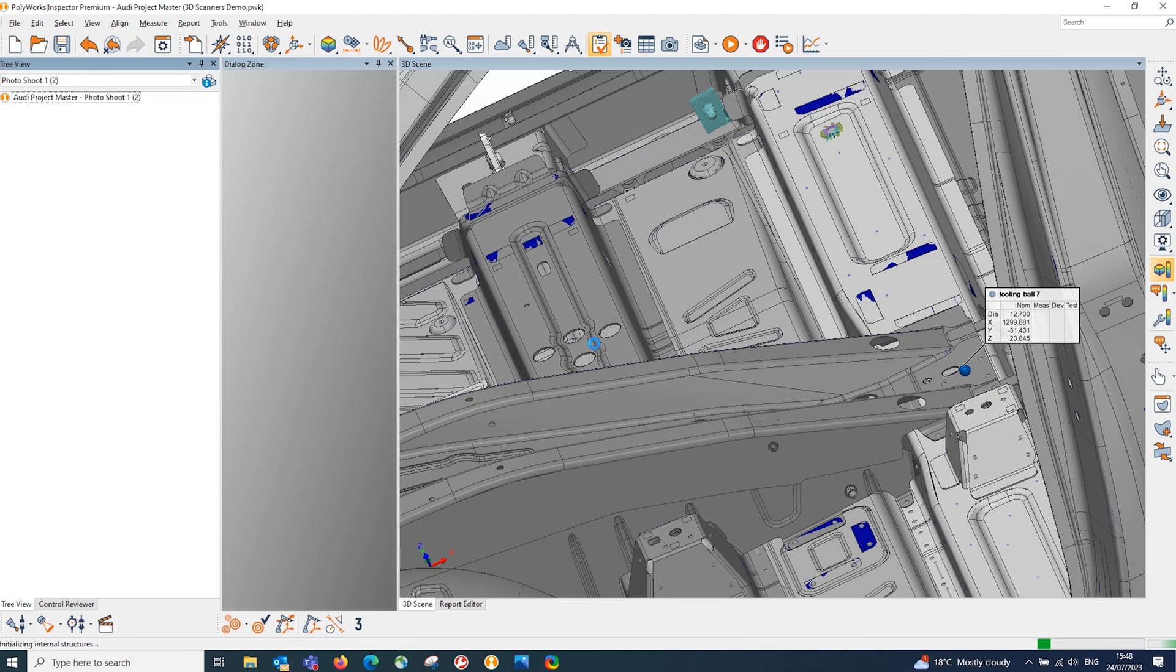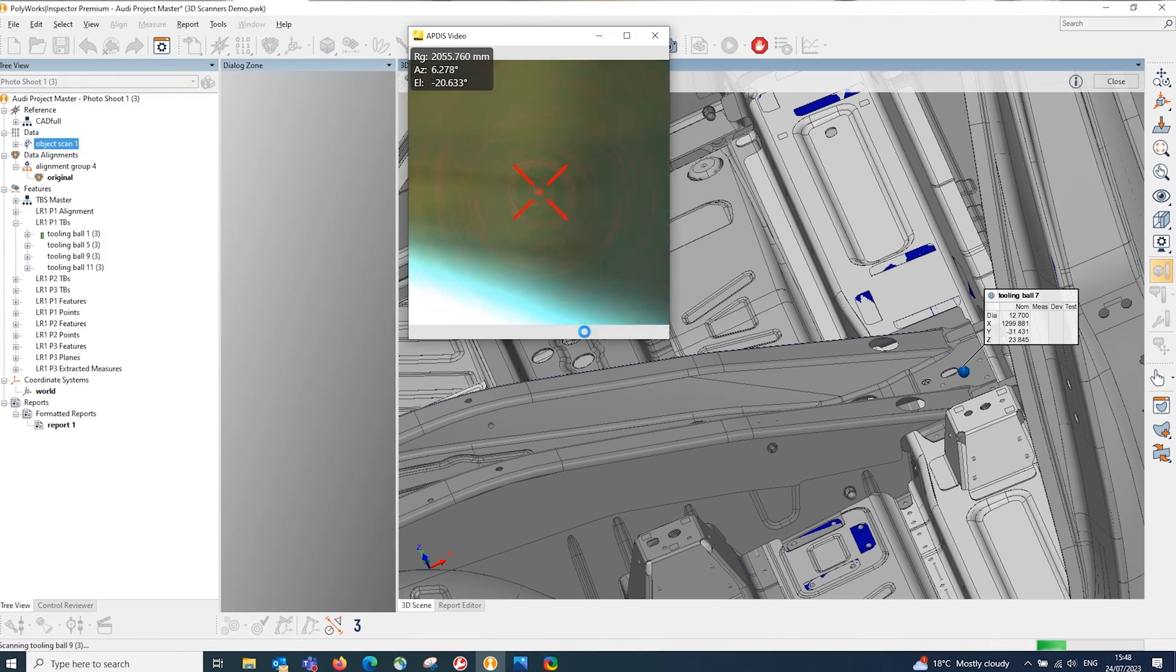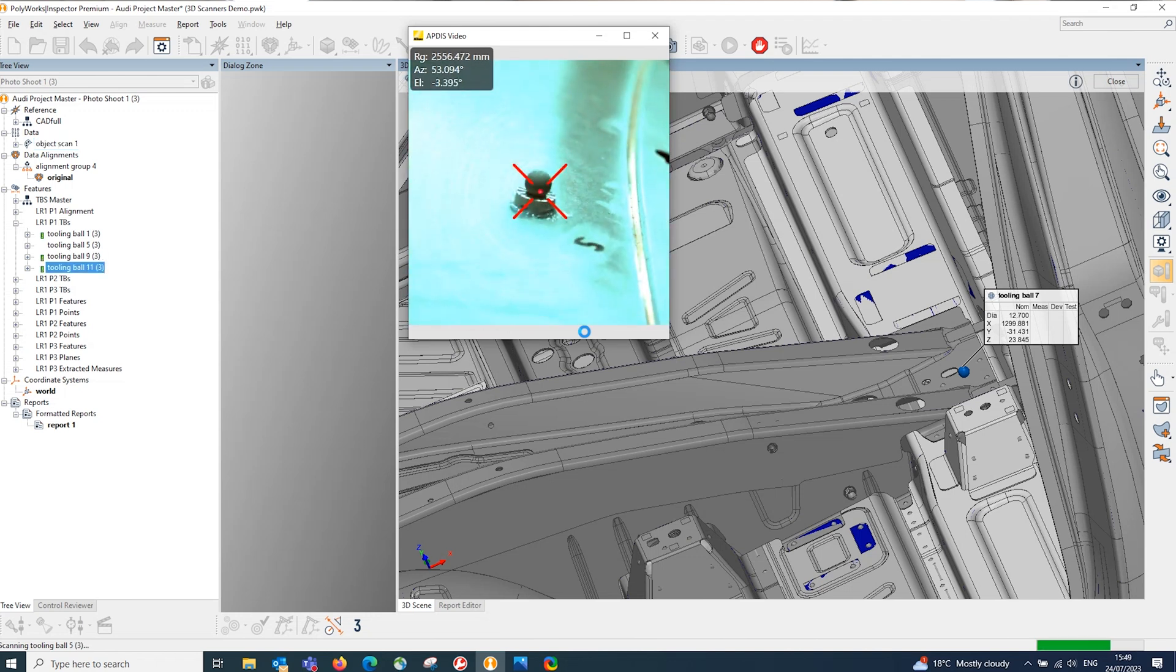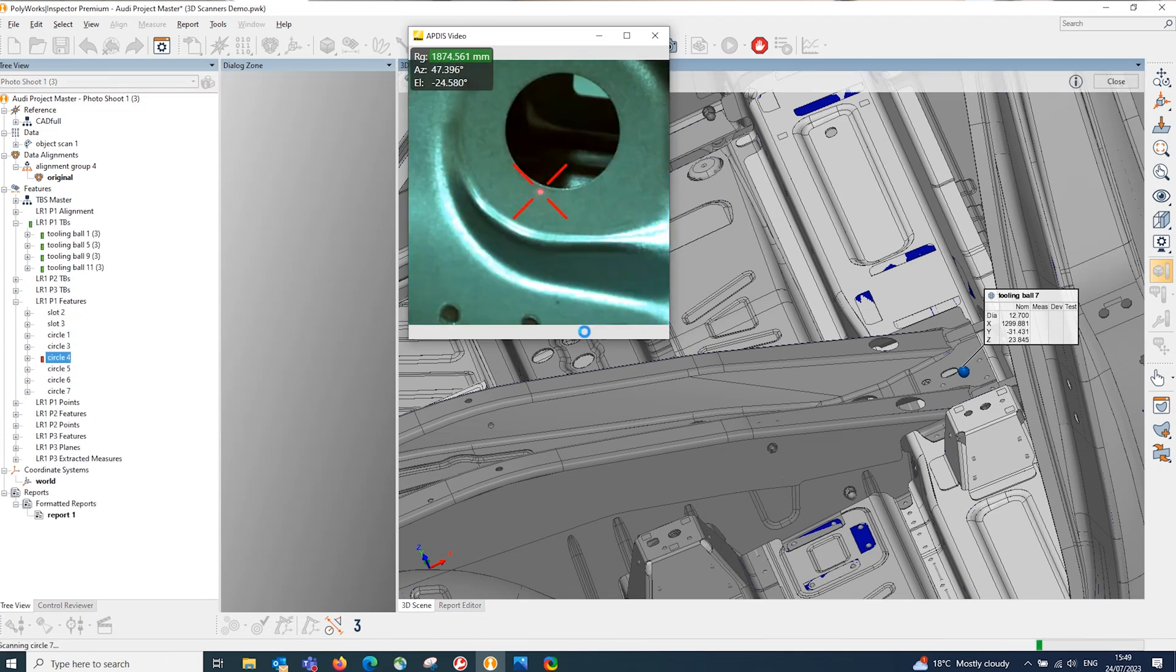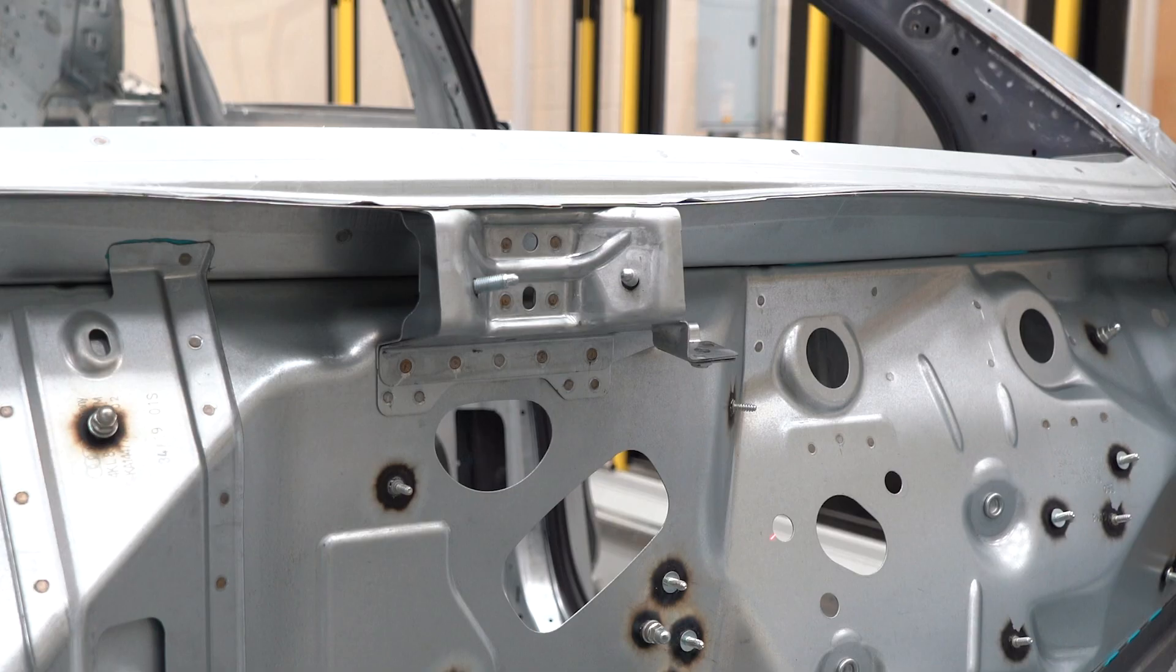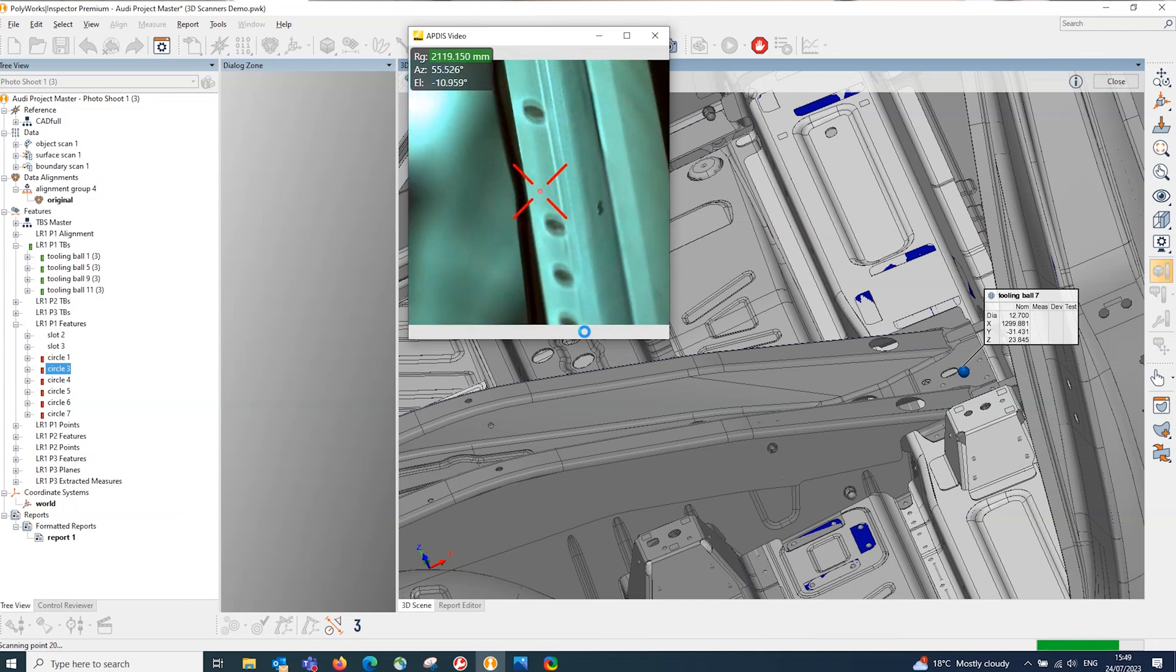From understanding the beauty about the system - correct me if I'm wrong Lucy - there are two variants of these systems? There are yeah, we have our standard version and we also have the enhanced. The main difference is the speed - the standard measures at 500 points per second and the enhanced is at 1000 points per second. With the enhanced version it will optimize the scan path so it'll move through the measurements in the most optimized way using our gauging engine software. It will work out what is the quickest path to measure. If your measurement cycle time is of the most importance you can really take that down.